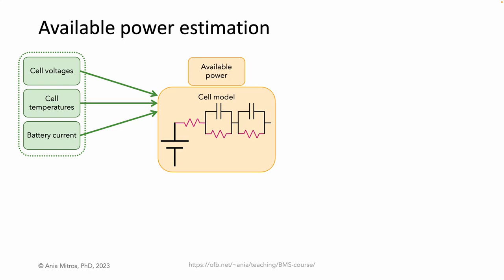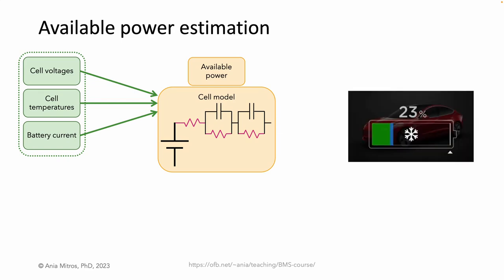It is important for the BMS to estimate how much power it is okay to put into or pull out of the battery. For example, when the battery is cold, it cannot provide full current. It also has a higher impedance, so when we pull current out, we will see the voltage droop more than at room temperature. The BMS must communicate to the charger whether the battery is able to accept charge, and if so, at what rate. The BMS must similarly communicate to its load, a motor or an inverter, at what rate it can extract energy.